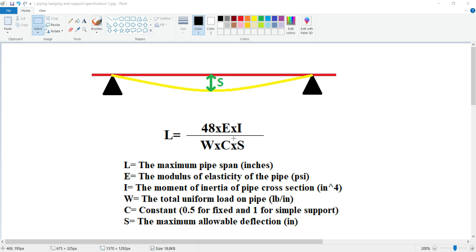The most important factor in maximum pipe span calculation is S because it is different in every project. For example, in some projects for main process services it might be considered as 7 or 8 millimeters, but for utility piping systems it can be considered around 12 or 13 millimeters. It really depends on project specification and the standards that you are using. This is an important factor that should be found in project specification to find out the allowable deflection in your system.